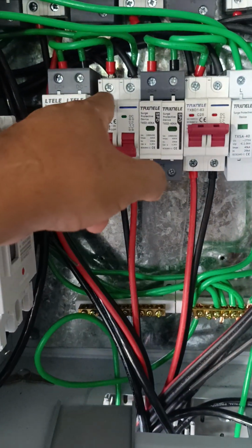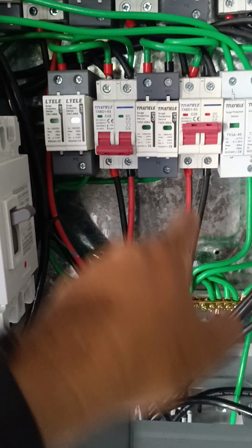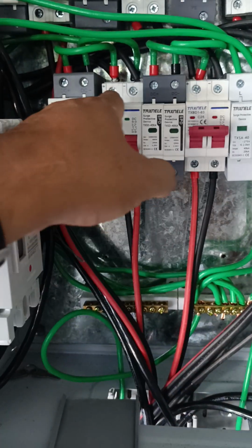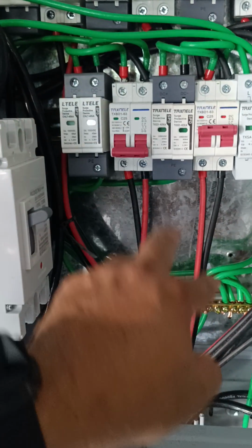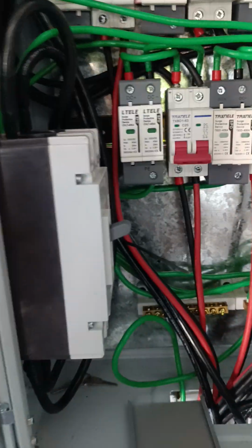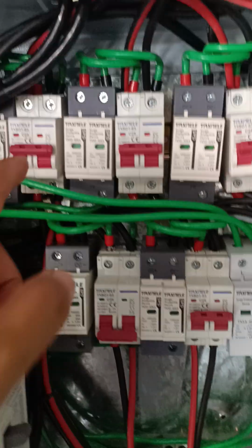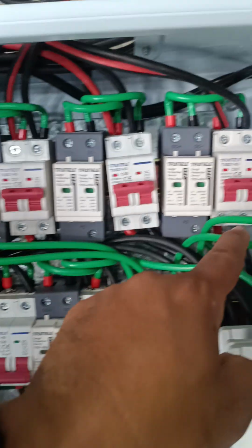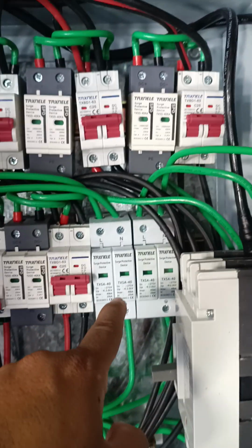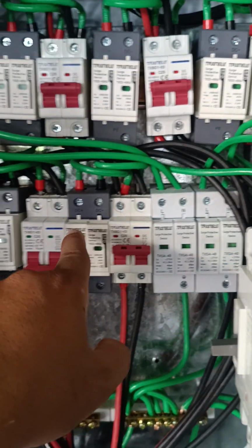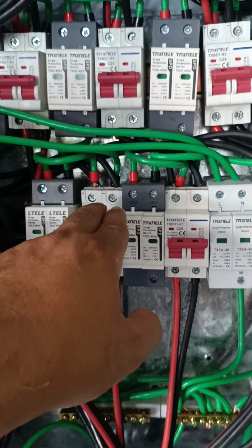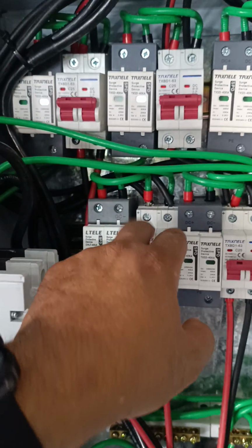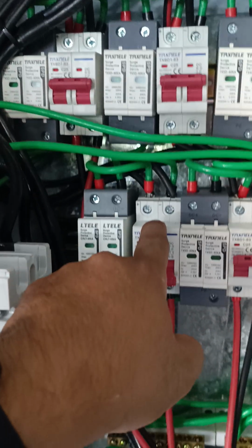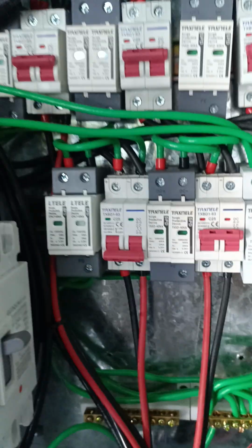We noticed that this string that is affected is beeping, which means it is connected to the ground, to the earthing, while the other 5 strings are not beeping. So that's how we found out that this particular string has a problem.